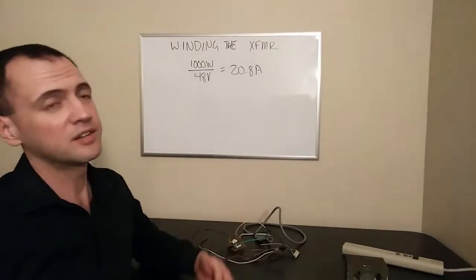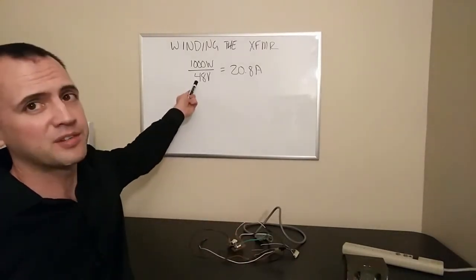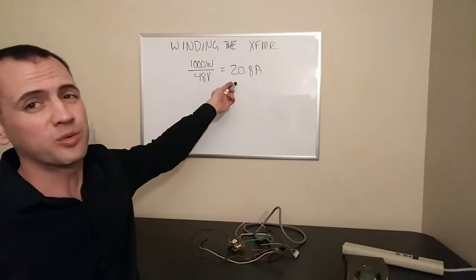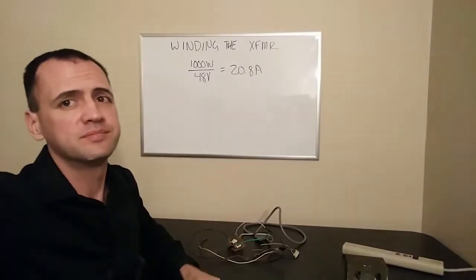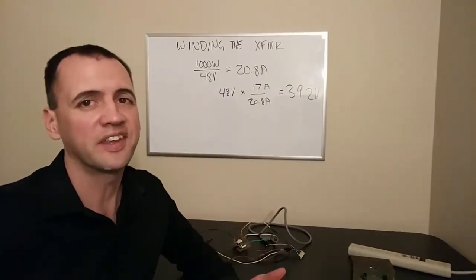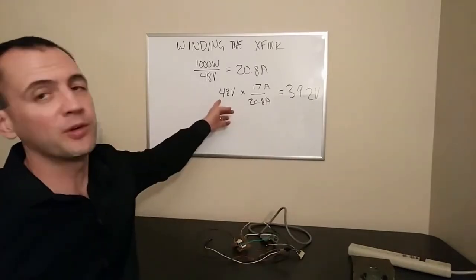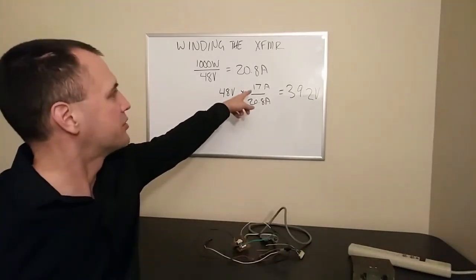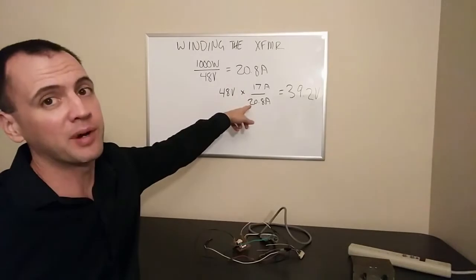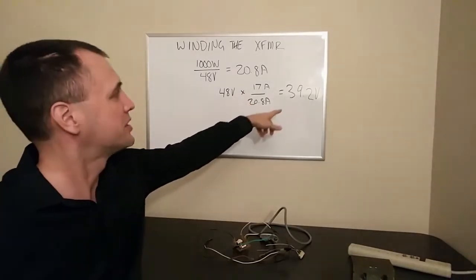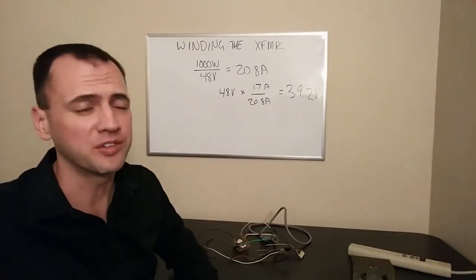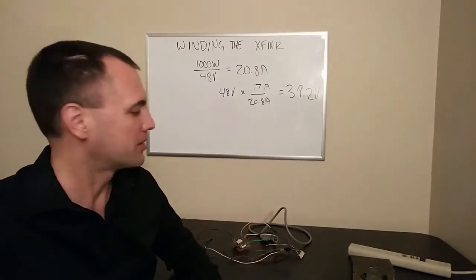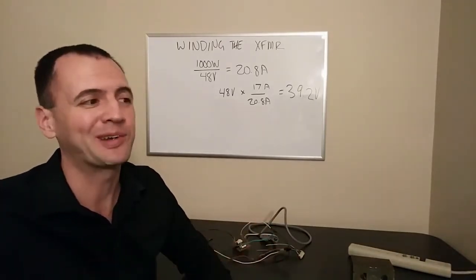So the first thing I did was divide the 1,000 watts by 48 volts to get 20.8 amps. Then the next thing I did was take that 48 volts, multiply by the ratio of the amperage we want to work at, divided by the amperage it's going to draw at full voltage, and I got 39.2 volts. This is going to be a safe estimate.